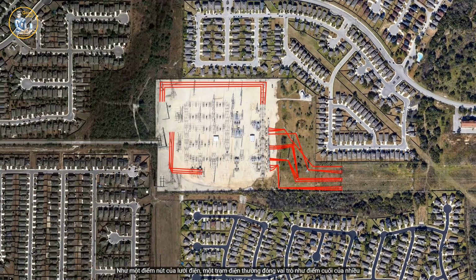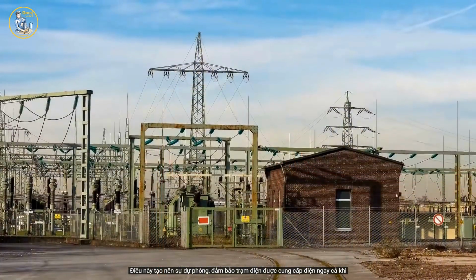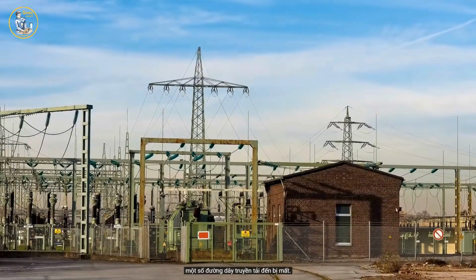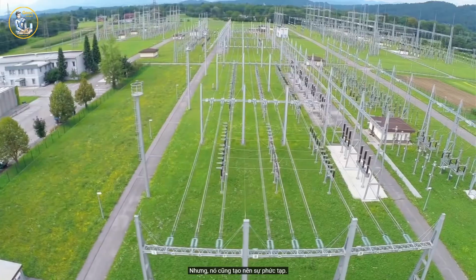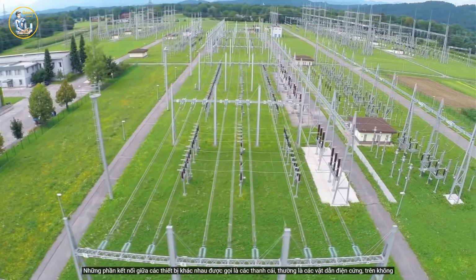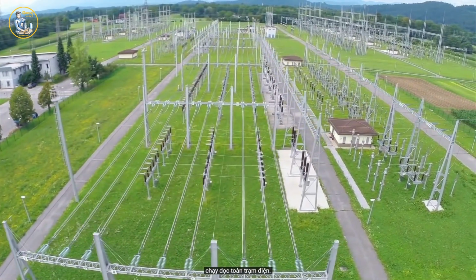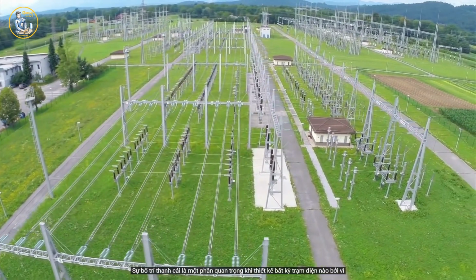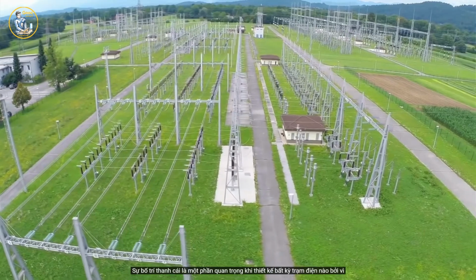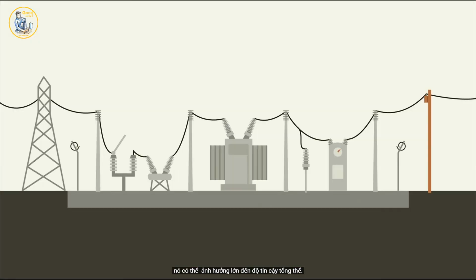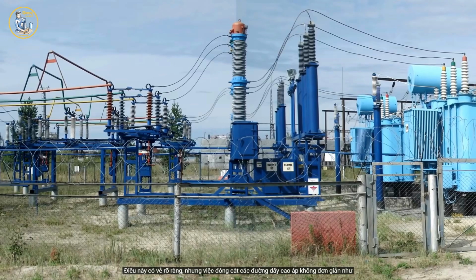As a junction point in the grid, a substation often serves as the termination of many individual power lines. This creates redundancy, making sure that the substation stays energized even if one transmission line goes down. But it also creates complexity. The connections to these various devices are called buses, often rigid overhead conductors that run along the entire substation. The arrangement of the bus is a critical part of the design of any substation because it can have a major impact on the overall reliability. Like all equipment, substations occasionally have malfunctions or things that simply require regular maintenance. To avoid shutting down the entire substation, we need switches that can isolate equipment, transfer load, and control the flow of electricity along the bus.